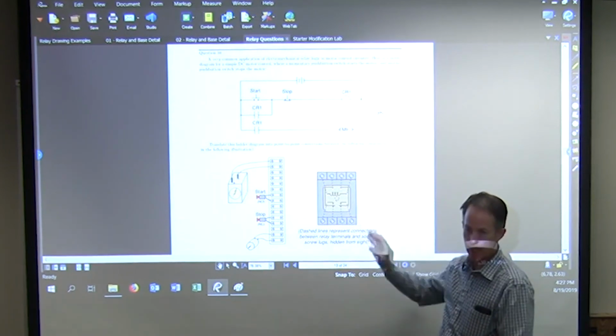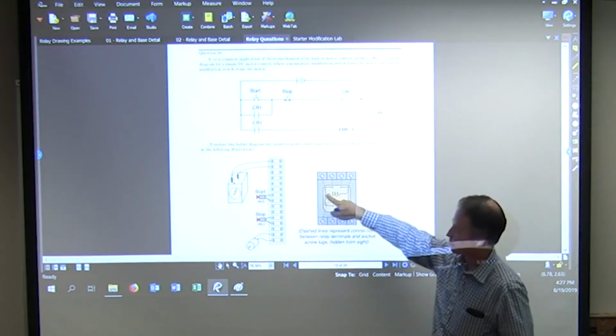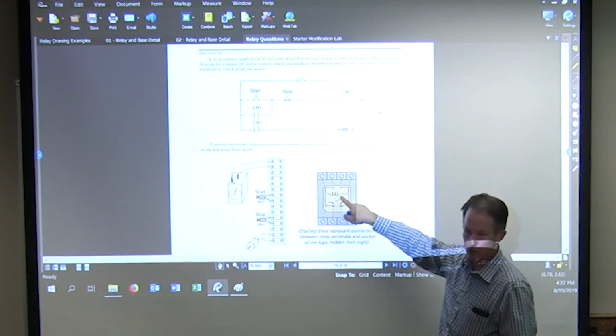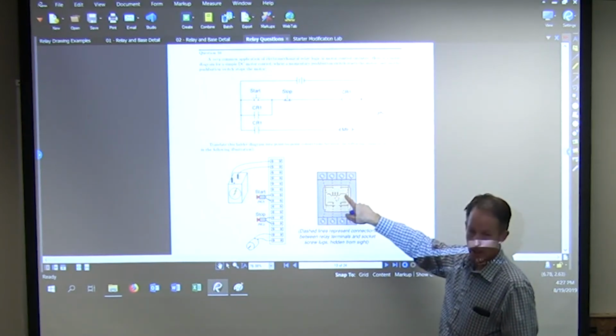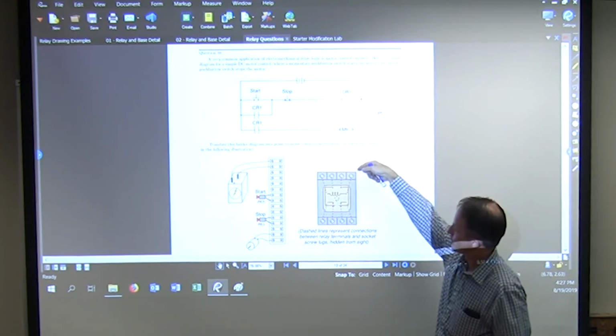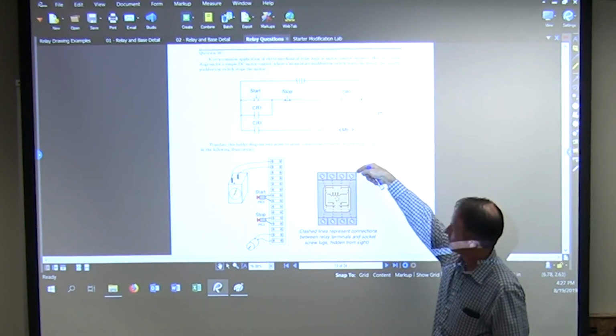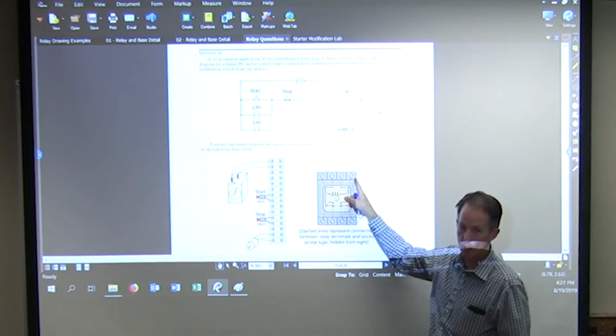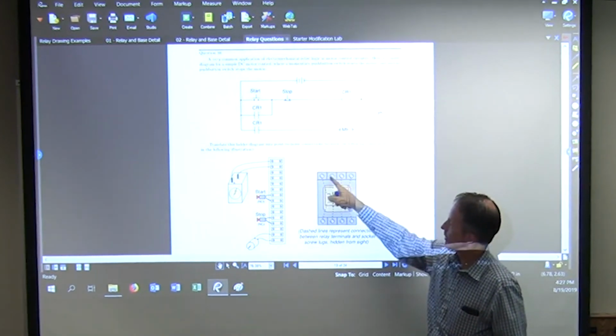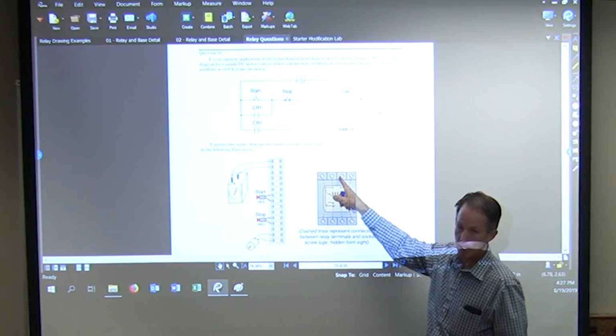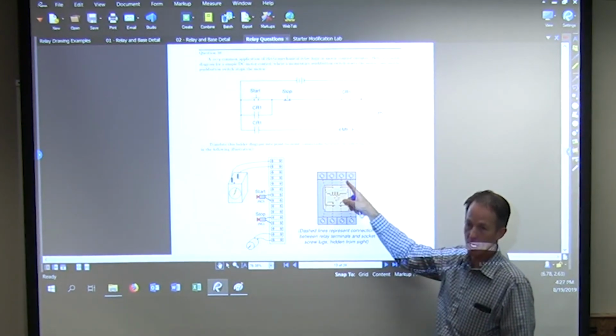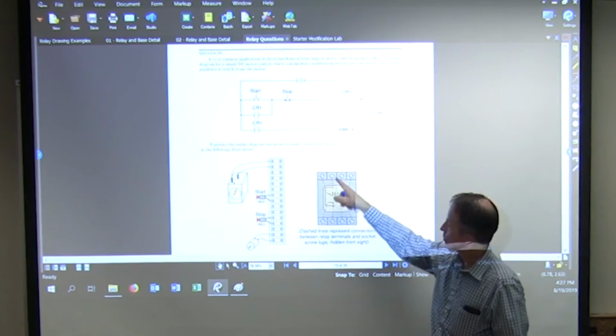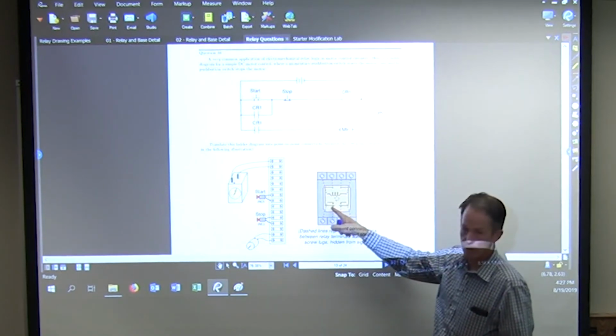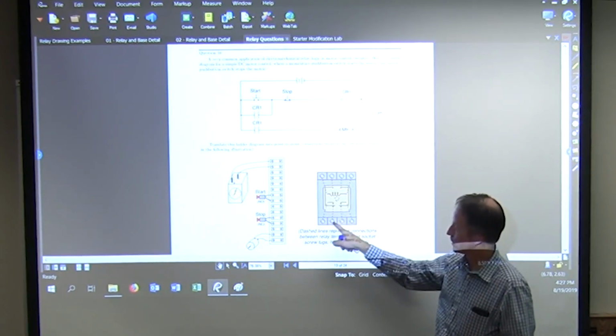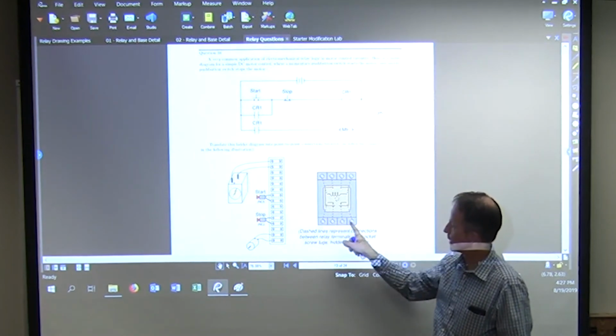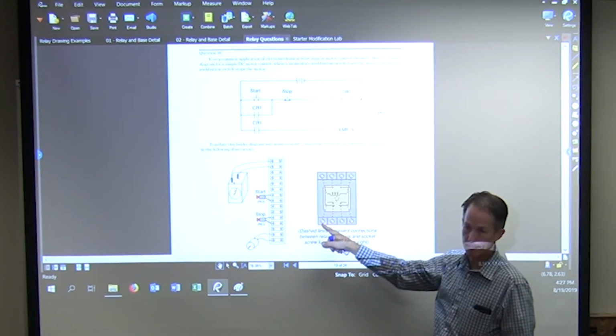On the relay base, the coil is the little curly Q wire in the middle, with the coil wires coming to the top outside corners. Those outside corners are the coil connections. The interior, or two at the top middle, are the commons for each of the two contacts, which come down to the normally closed contacts. The normally closed are the interior ones, and the normally open are on the outside bottom.